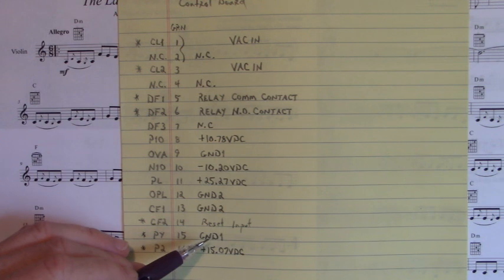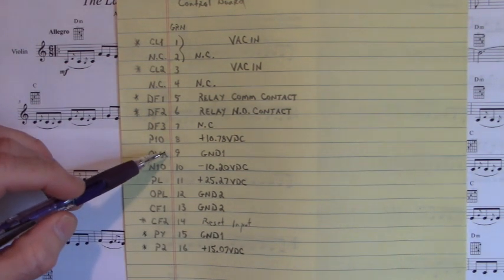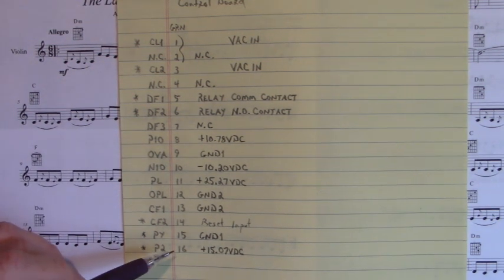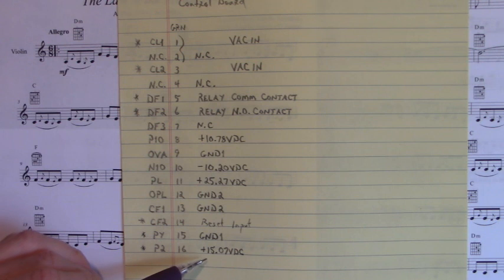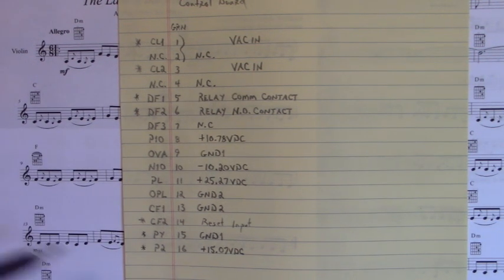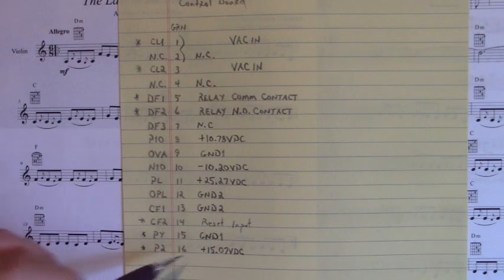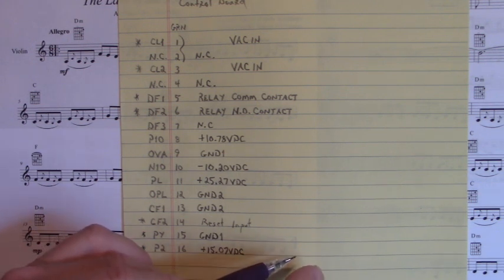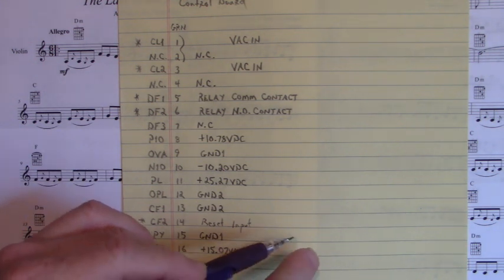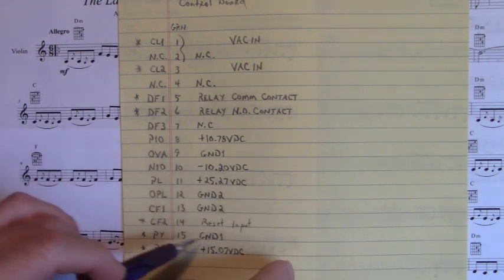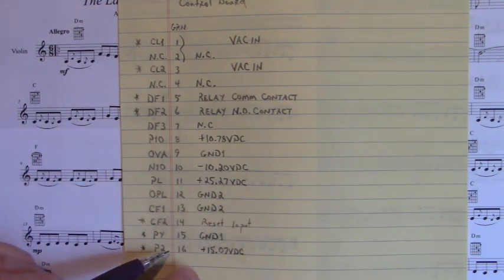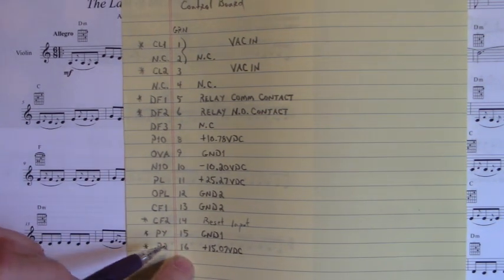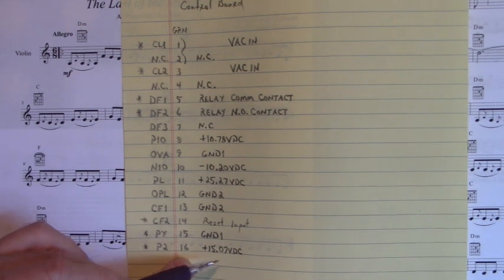Down here on 15, we have ground 1 again. That's tied to terminal 9. And terminal 16, we had 15.07 volts DC. Now I followed terminal 16 back in, and it went to a heat sink thermal on one side. So here on 16, the wires went to a heat sink thermal internal to the bus power supply, and I don't know where the other side of the heat sink thermal went to, but when I measured 16 to 15, I had 15.07 volts DC.